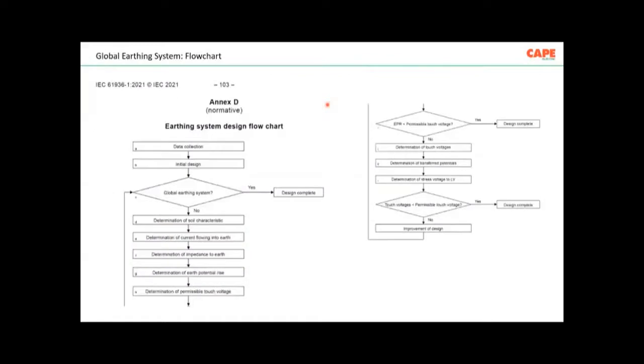How do we measure and what kind of things are required? I'm just showing you the page from the risk assessment in IEC 61936. Earthing system design flowchart: data collection, initial design, global earthing system, yes, design complete. If you are doing a global earthing system, you don't need to do all these parameters such as soil characteristics, current flowing to earth, impedance to earth, earth potential rise, permissible touch voltage. All these calculations are simply not required.